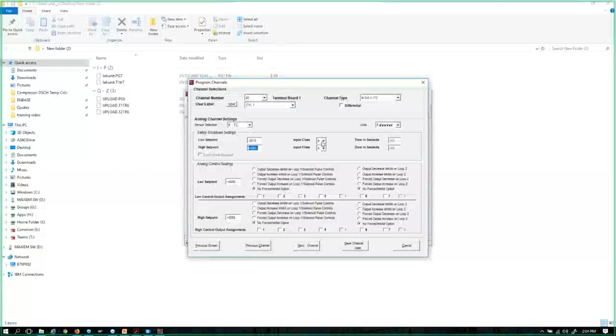I'll keep it as a class A. And then again, my high kill in this case is 265. And it's also a class A. But because they're both class A's, it's not part of the cool down availability function. We can change the units from Fahrenheit to Celsius. And of course, it throws off our shutdown set points a little bit, and it just gives us a note to correct them if we need to. And I can keep it back as Fahrenheit.